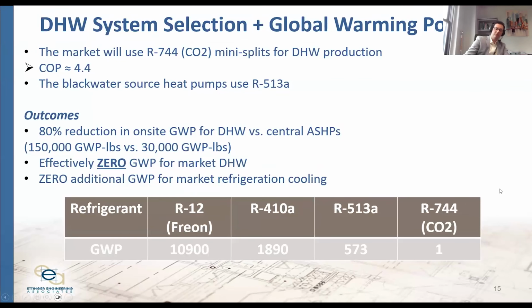A couple words on the global warming potential of this. It's obviously much more dramatic for the HVAC system with 3 miles of piping, but these systems are more centralized. The blackwater source heat pumps I spoke about use an advanced refrigerant, R513A, and the global warming potential of that is roughly one-third of R410A. So that's victory number one.